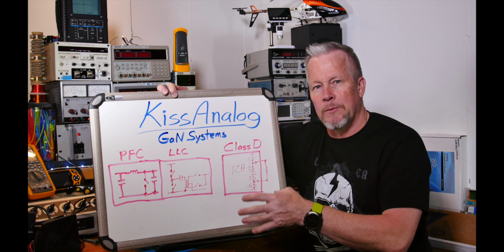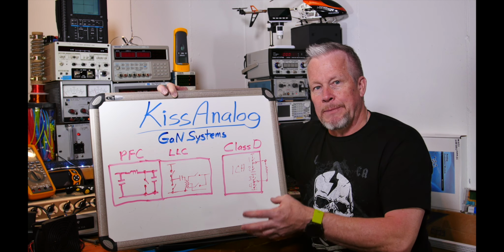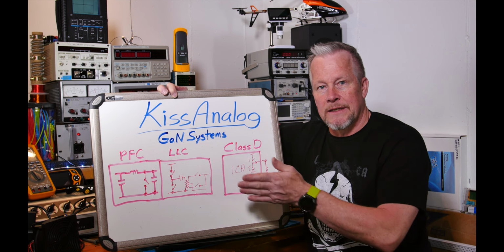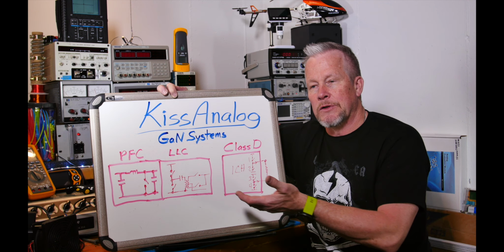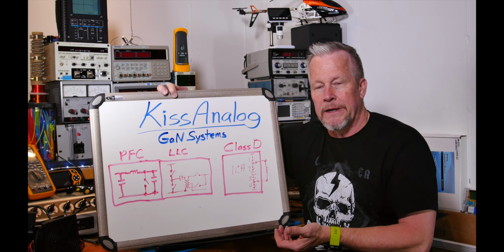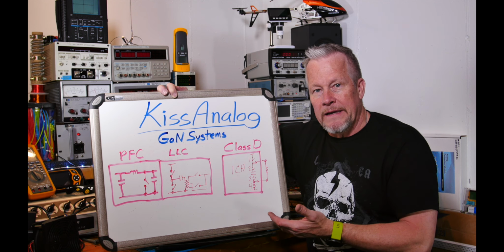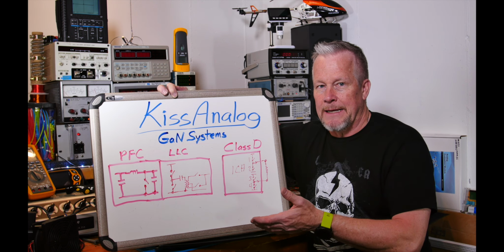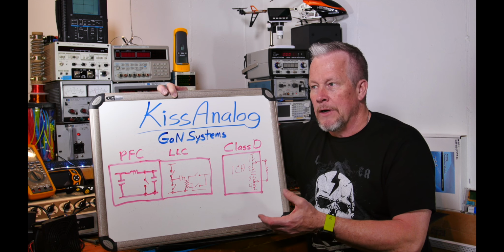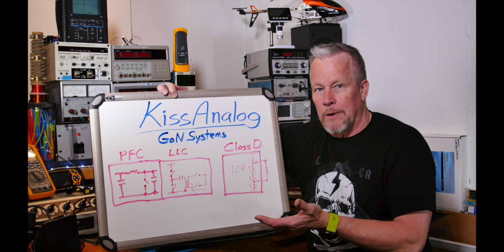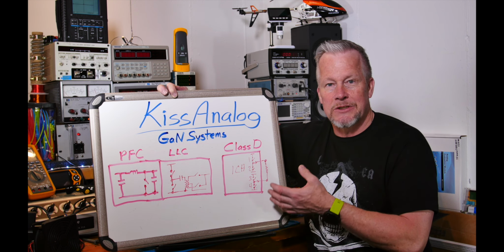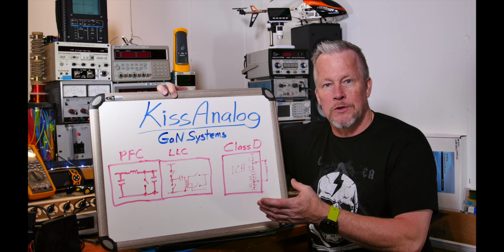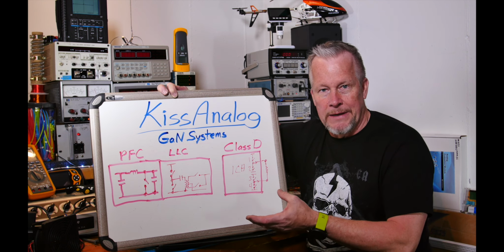So in the case of a normal power supply, there's power going in. You monitor current and voltage, and you go, well, there's 100 watts going in, but that's called VA because it's volts times amps. The actual real power might only be 40, 50, or 60 watts, because it's so bad - the current and the voltage are badly put out of phase.